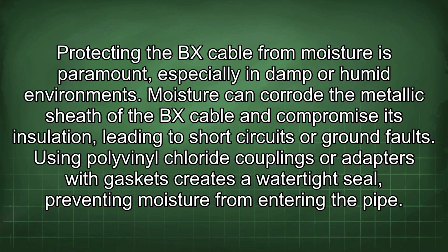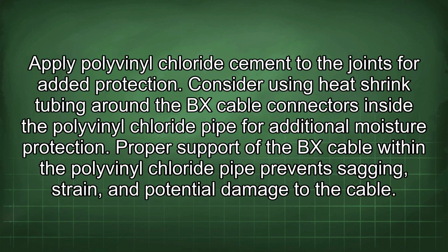Protecting the BX cable from moisture is paramount, especially in damp or humid environments. Moisture can corrode the metallic sheath of the BX cable and compromise its insulation, leading to short circuits or ground faults. Using polyvinyl chloride couplings or adapters with gaskets creates a watertight seal, preventing moisture from entering the pipe. Apply polyvinyl chloride cement to the joints for added protection. Consider using heat shrink tubing around the BX cable connectors inside the polyvinyl chloride pipe for additional moisture protection.